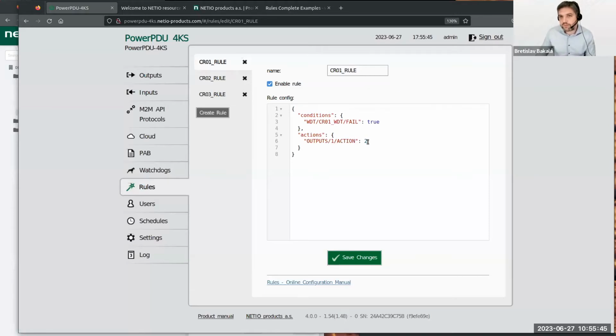This number is specific because we have different types of commands. 0 is switch off, 1 is switch on - straightforward and clear. 2 is short-off, meaning the device automatically switches off the output, and after the specific delay, as Rick asked, it will turn on automatically. This is good when, for example, you have a router or connectivity device connected to the output, and you cut the connection branch to that device.